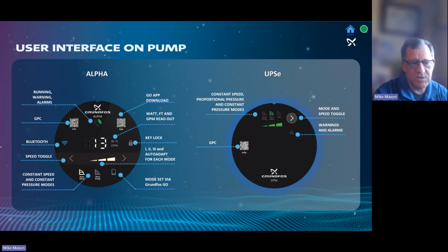One little note is if you have it set up through the phone and you want to just test something, you want to run it real quick at, say, a constant curve. I've done this, it works pretty well. If you touch the constant curve, it'll take it to that, and you can run it through that speed, do whatever you want to check. And then if you just touch the phone icon again, it will put it back into the same mode that it was before. Whatever was set will still be set.